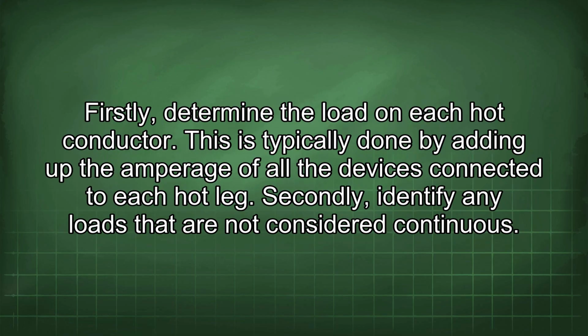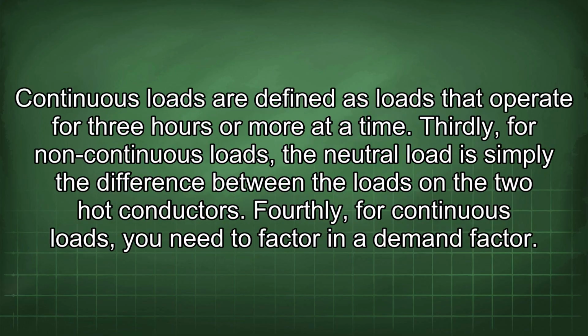Firstly, determine the load on each hot conductor. This is typically done by adding up the amperage of all the devices connected to each hot leg. Secondly, identify any loads that are not considered continuous. Continuous loads are defined as loads that operate for 3 hours or more at a time. Thirdly, for non-continuous loads, the neutral load is simply the difference between the loads on the 2 hot conductors.